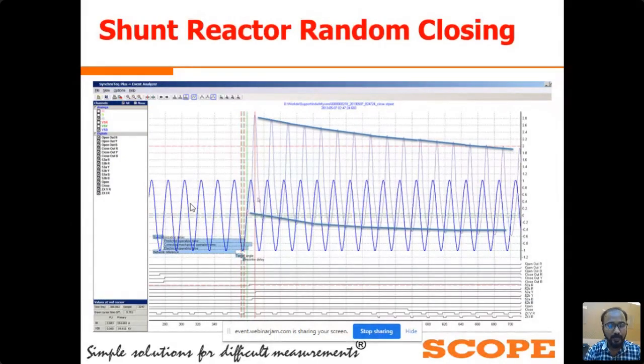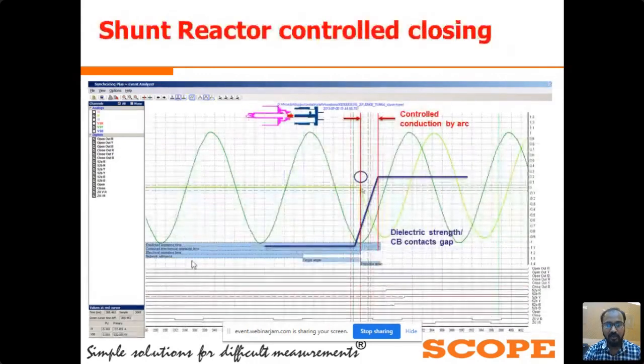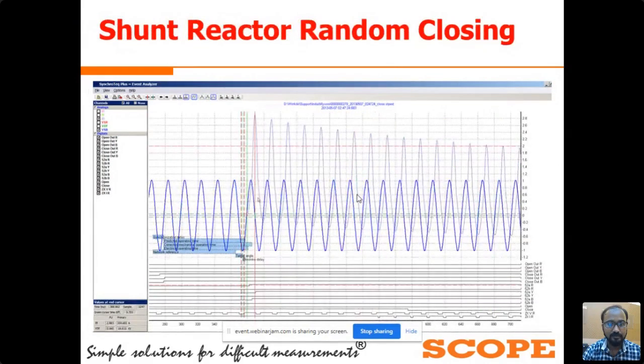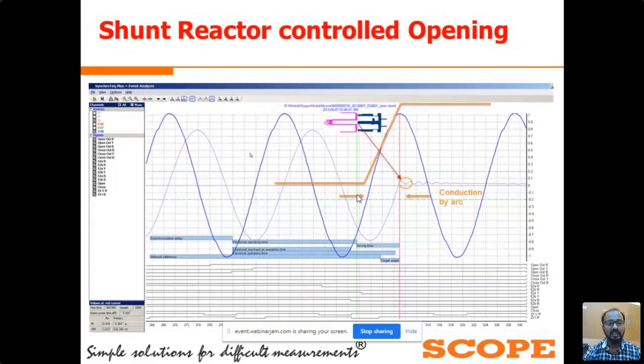So to minimize this type of DC asymmetry at the time of closing of the shunt reactor, we are using the controlled switching device. By targeting the voltage peak point, we can minimize this type of DC asymmetry during the closing of the shunt reactor. So this is an example of shunt reactor closing with and without controlled switching. Now we will see the controlled opening of the shunt reactor.